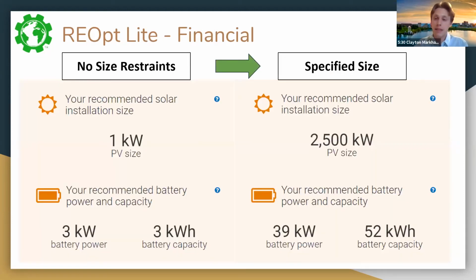Then we used REOpt Lite, which suggested to us the best battery size and dispatch strategy based on finances and a desired resiliency premium. On the left, we were recommended a 1 kilowatt PV, 3 kilowatt hour battery size with no size constraints, which shows just how difficult the rate structure we were working within was. When we then specified the 2.5 megawatts, we got a much larger battery.